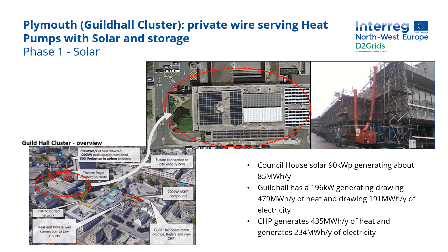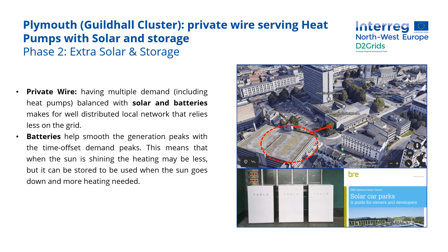The second phase took advantage of solar surplus to store it and use it later with private wire. Having multiple demands, including heat pumps, balanced with solar and batteries makes for a well-distributed local network that relies less on the grid. Batteries help smooth the generation peaks with the time-offset demand peaks. This means that when the sun is shining, the heating may be less, but it can be stored to be used when the sun goes down and more heating is needed.